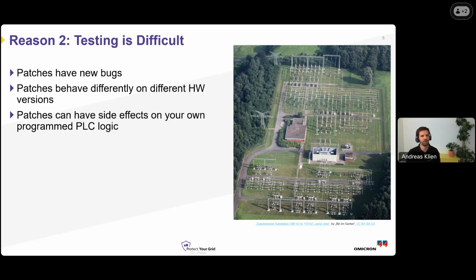The next point: you're programming this intricate logic with so many switching combinations. This needs to be programmed in PLC logic, the same as it's done in factory automation. The firmware update can have side effects on this PLC logic. I've talked to customers who told me they had flaws in the PLC logic which were triggered by the firmware update behaving slightly differently, and this can be different from substation to substation.